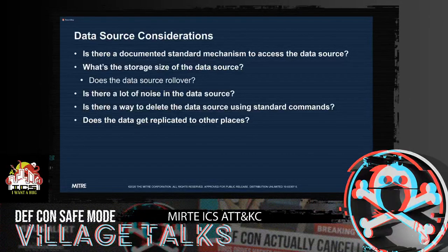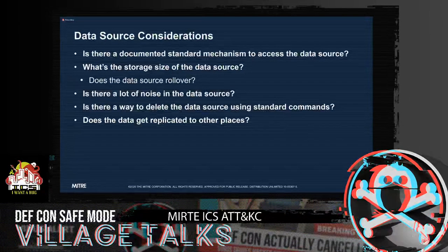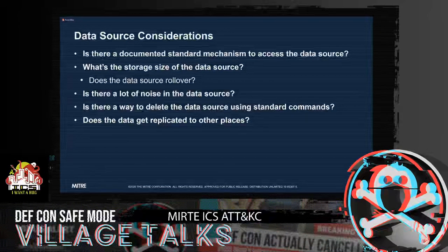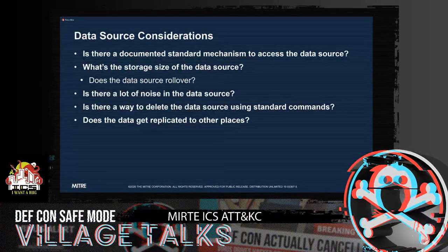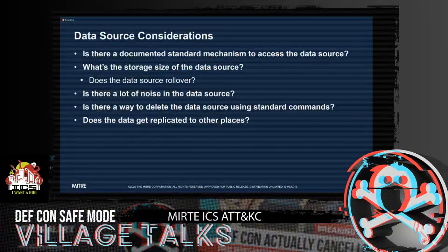Here are some data source considerations when working in these environments. Is this data source accessible via a standard documented interface? That's very important for access. What's the storage size — will it eventually roll over? Is there a lot of noise in the data source that would make it hard for a defender to look through it? Are there standard commands available to just delete that data source? And does the data source get replicated elsewhere? If we're looking at a low-level protection relay, does data go up to another controller? There may be aggregation points somewhere — these are all things we have to consider.